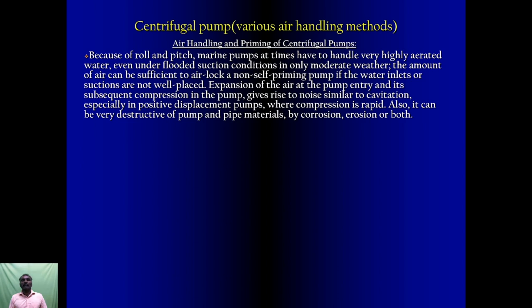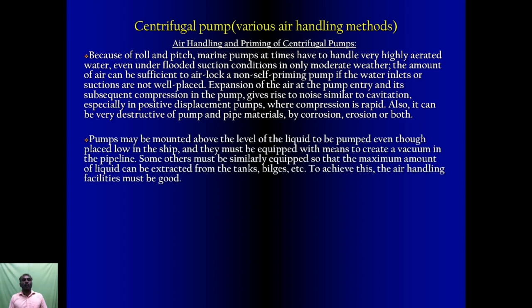Expansion of the air at the pump entry and its subsequent compression in the pump gives rise to noise similar to cavitation, especially in positive displacement pumps where the compression is rapid. Also, it can be very destructive of pump and pipe material by corrosion, erosion or both. Then, pumps may be mounted above the level of the liquid to be pumped even though placed low in the ship, and they must be equipped with the means to create a vacuum in the pipeline.